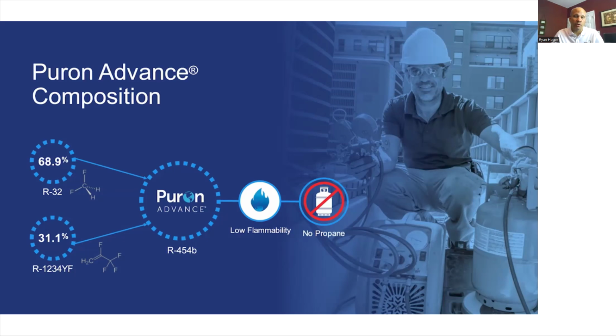In the case of R410A, we mix the R32 with R125, which is a flame suppressant, and when combined, we have a non-flammable entity. However, in the case of R454B, we have more R32. We have 69% instead of 50, and we're mixing with 1234YF, which is also a flammable A2L refrigerant. So we've got two A2L flammable refrigerants mixed together. That means R454B will also end up being an A2L flammable refrigerant.